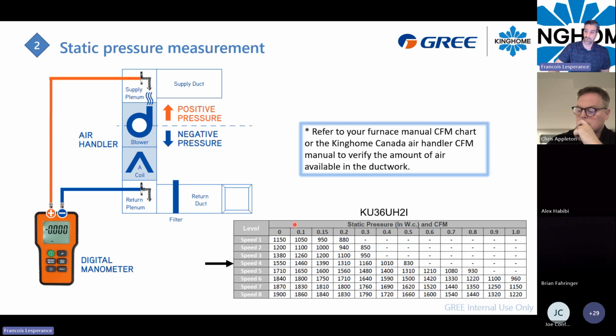So you can refer to the chart of CFM. For example, this is a 3-ton unit, on the Kinghome air handler, and by default, we know that we are always at speed 4. So regarding the static pressure I have right here, I can refer to my measurement here, and I can already know the amount of CFM going in my supply duct. By doing this at the first startup of the unit, this is really helpful for you guys to manage if you have some airflow issue right at the beginning.